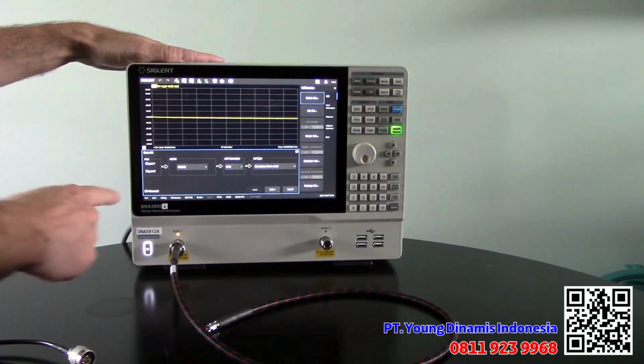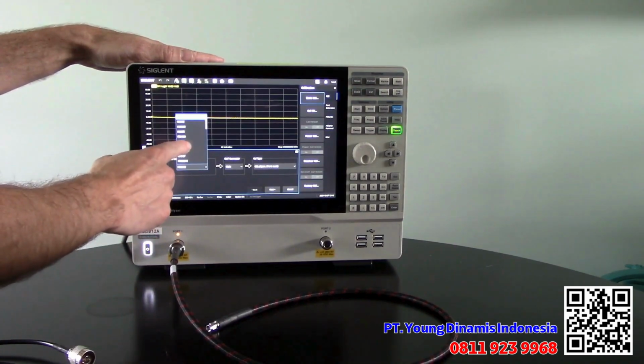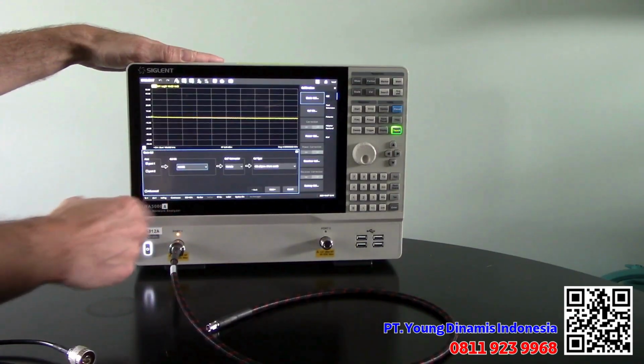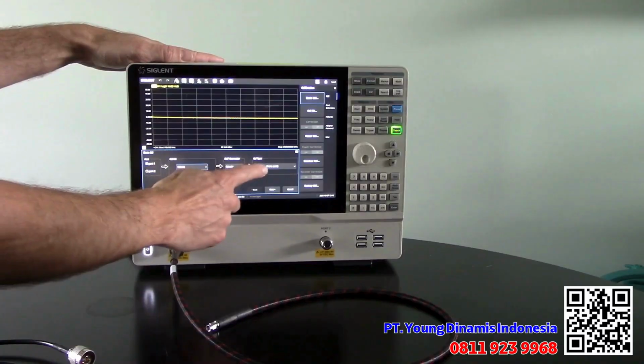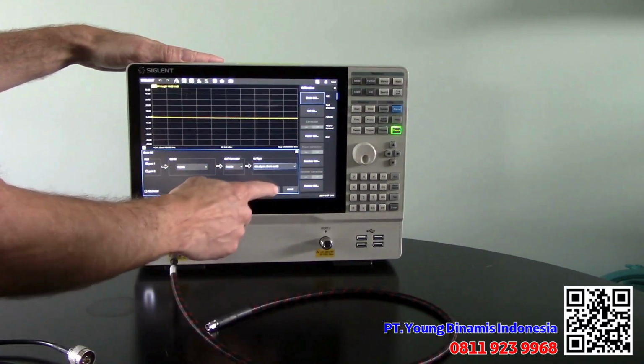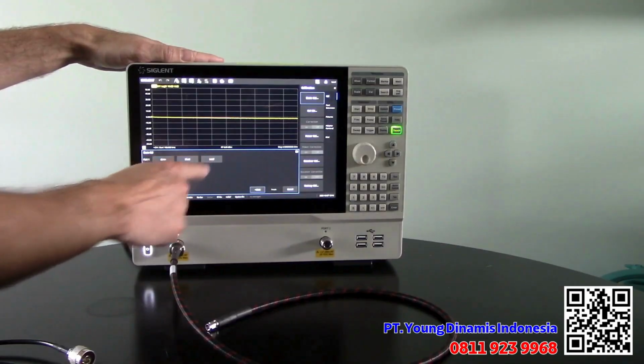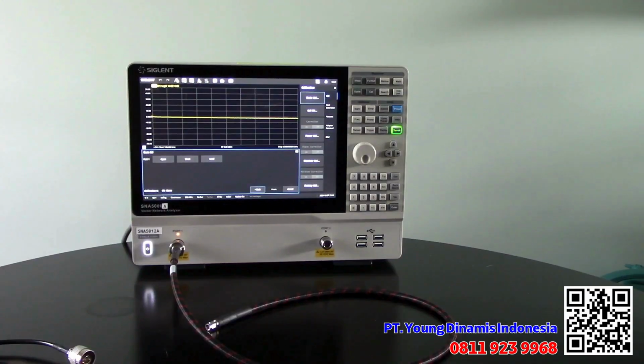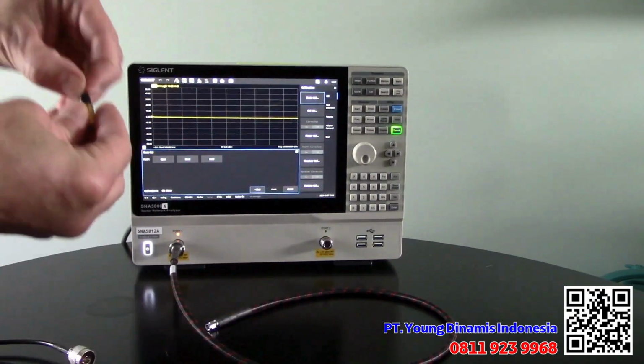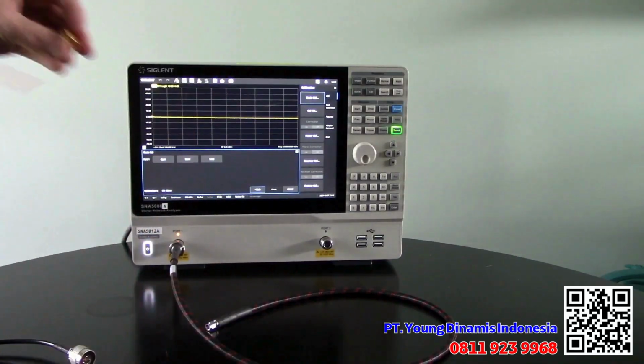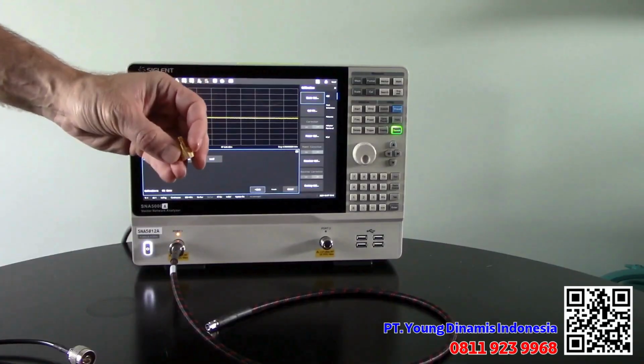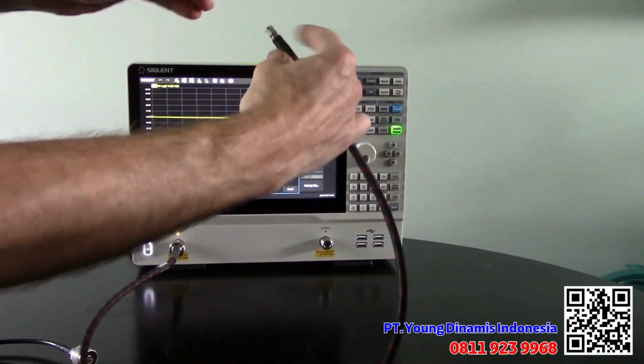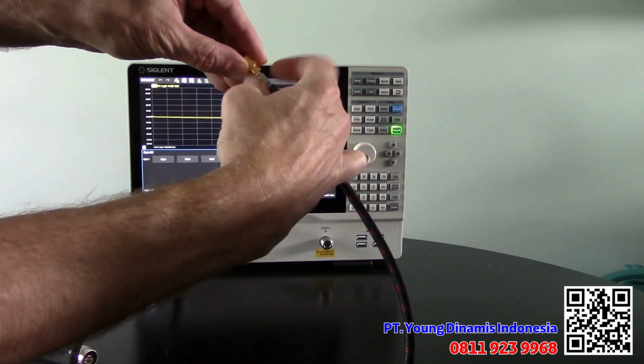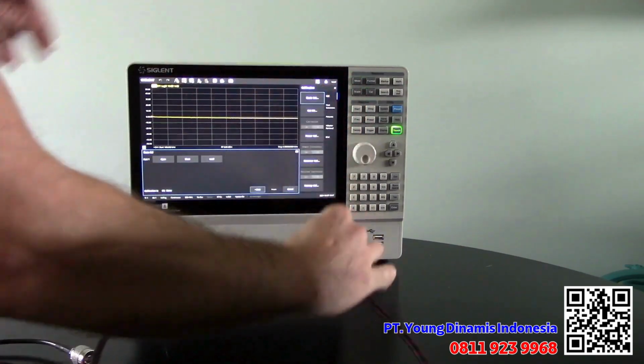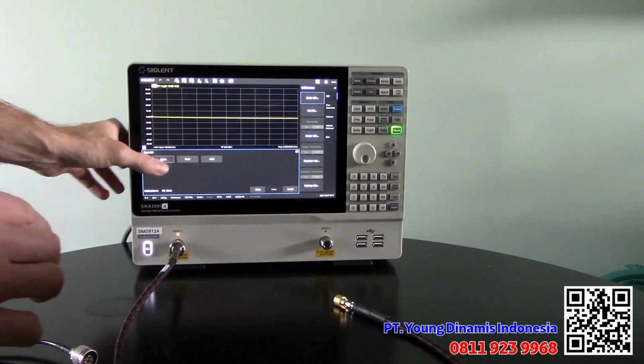So we're going to go into the calibration menu for the SNA 5000. We're going to select our calibration kit. That is the F604, and then we're going to perform the short, open, and load test. So we're going to select that out of the menu, and we're going to start the calibration. It's going to prompt us to put the short, open, and load calibration kit elements onto the cable. So we're going to start with our open, pull that cap off. We've already cleaned this, but we're going to just give it a quick shot to get rid of any dust that might have accumulated. And we're going to turn the barrel of the connector and tighten that. We're not going to spin the actual calibration element. We're going to spin the barrel, and that's going to prevent any damage to that center conductor.